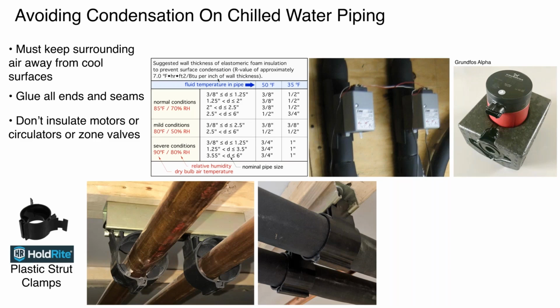One of the things that I'm kind of on a crusade for right now is trying to get more pump manufacturers to offer these insulation shells as we move into systems with heat pumps, and this potential for chill water cooling in smaller scale buildings is certainly going up. We need to be able to insulate the circulators. This Grundfos Alpha product, you can buy an insulation shell.